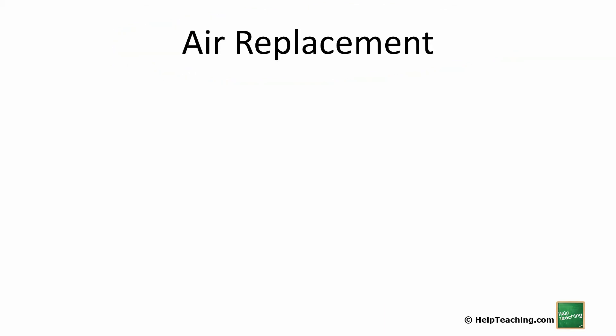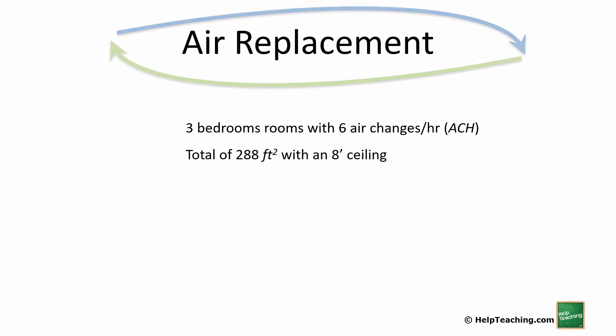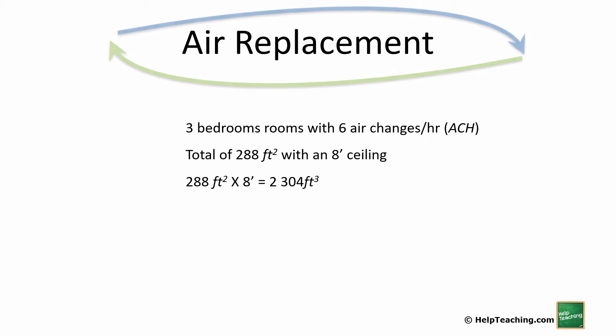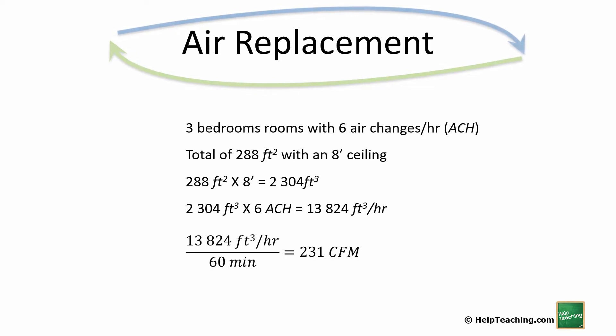For three bedrooms with 6 air changes per hour, I've combined the total square footage instead of breaking it into three separate rooms. We have a total of 288 square feet with an 8-foot ceiling. Calculating square feet times height gives us a volume of 2,304 cubic feet. Six air changes brings us to 13,824 cubic feet per hour. Dividing by 60 gives us 231 cubic feet per minute.